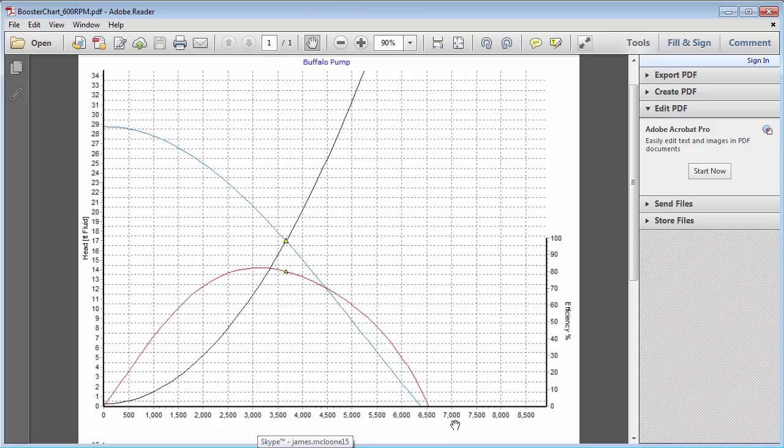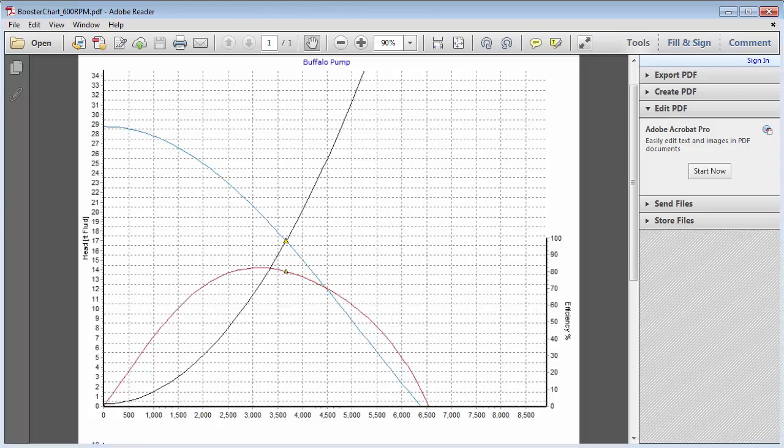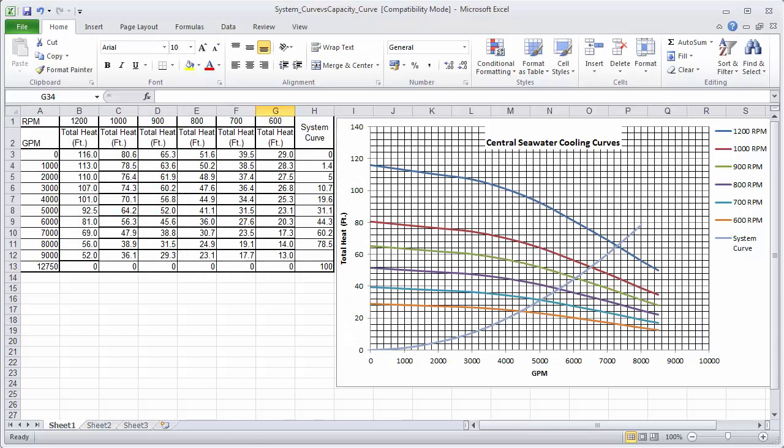On further review of the template Excel file we identified that in determining the revised pump capacity curve the affinity laws had only been applied to the head value and not the corresponding flow value. This resulted in the generation of an erroneous curve in Excel which gave misleading and incorrect pump performance data.